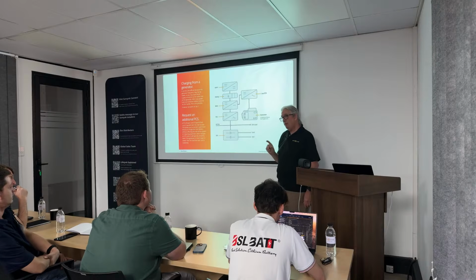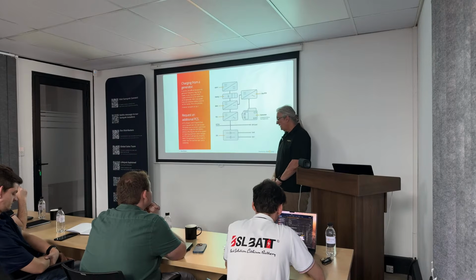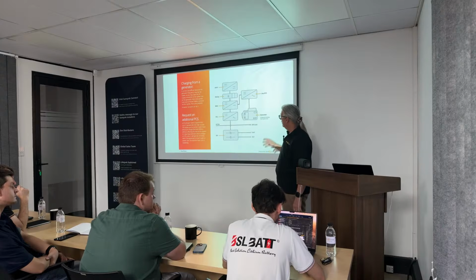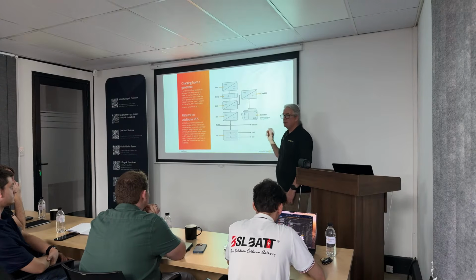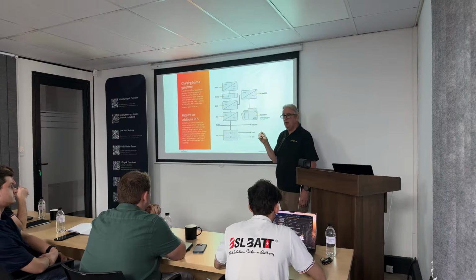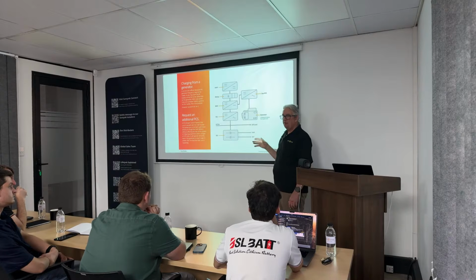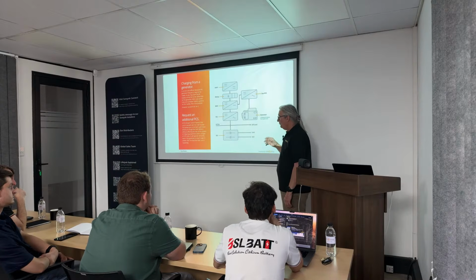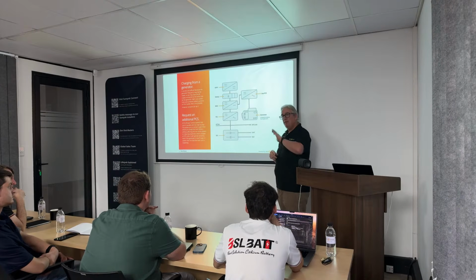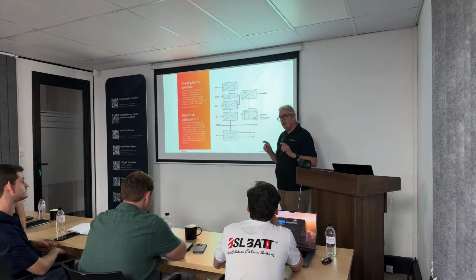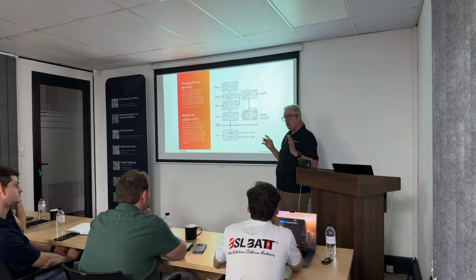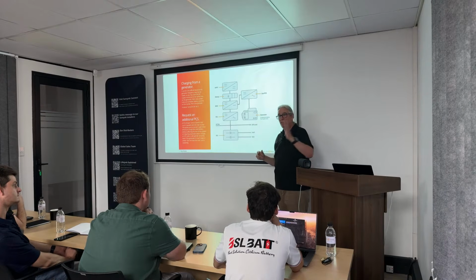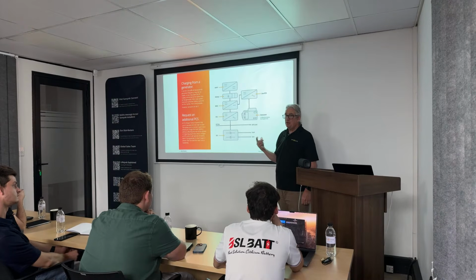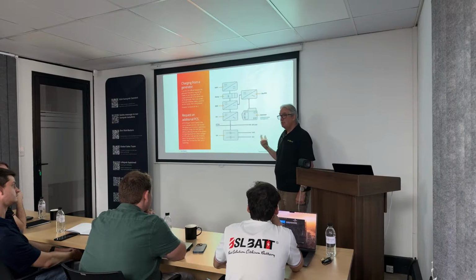Be careful. One of the things to be careful about is what I was showing: we protect the export because it's a common bus, and we protect the export using a meter. We don't use CT cores on the big stuff now, so it's done by a meter. There is a possibility for it to backfeed, so we have to be very, very careful on that, especially with a generator, because the last thing you want to do is backfeed the power into a generator and blow a generator up. If you are directly connecting a generator to the AC bus on a hybrid inverter that can export, then make sure the generator is big enough.